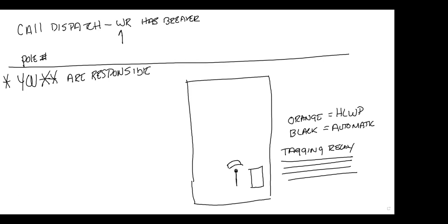So the question reads, on the breaker panel, how can I tell if there's a hotline work permit on the circuit? There will be a window with HLWP on it. There will be a handle for reclosing relay off with a red flag. The breaker light will be white. The local remote handle will be in local. There will be handle for the reclosing tagging relay that is orange. It'll be the tagging relay, which is orange. Tagging relay is orange. Just follow the colors. Yep. Okay, we need to fix that answer, Professor V. Okay. All right.